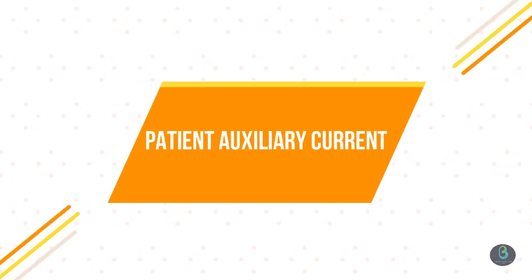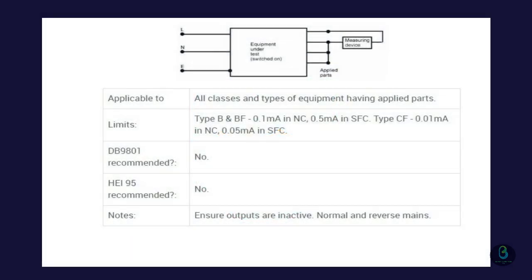Patient Auxiliary Current. Patient Auxiliary Current is measured between any single patient connection and all other patient connections of the same module or function connected together. Where all possible combinations are tested together with all possible single fault conditions, this yields an exceedingly large amount of data of questionable value.